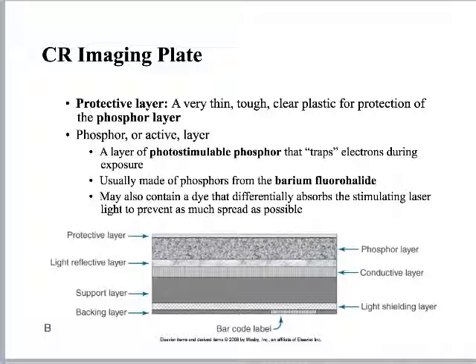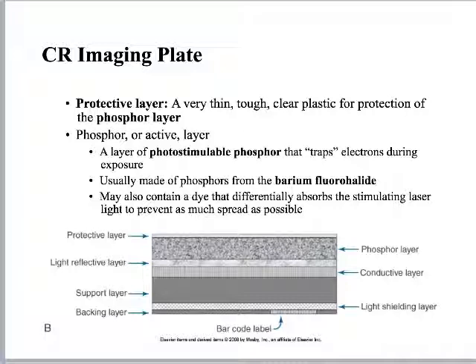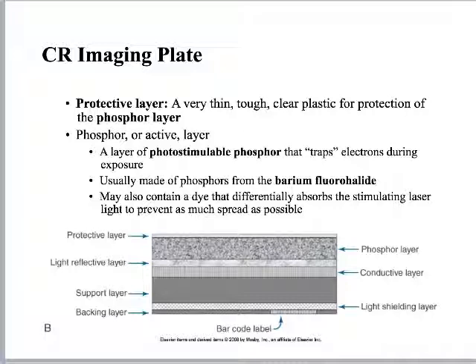There's a protective layer of clear plastic on the outside, and immediately beneath that is the phosphor or active layer — sometimes called the PSP. It has a photostimulable phosphor that is responsible for trapping electrons during exposure. X-ray photons produce ionization inside the PSP, and the crystal traps the electrons produced from that ionization. It is typically made out of barium fluorohalide. It is photostimulable, meaning it gives off light in response to stimulation. The barium fluorohalide glows blue-violet.